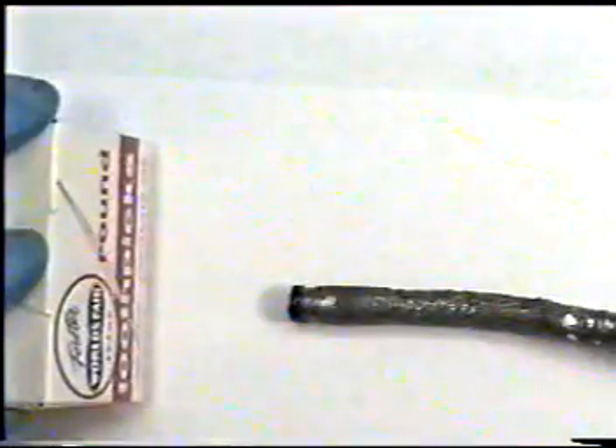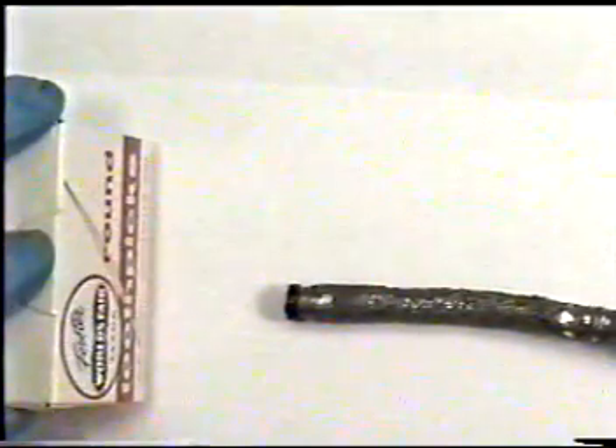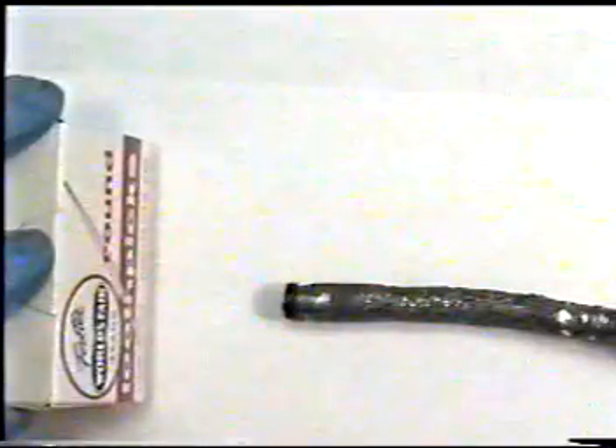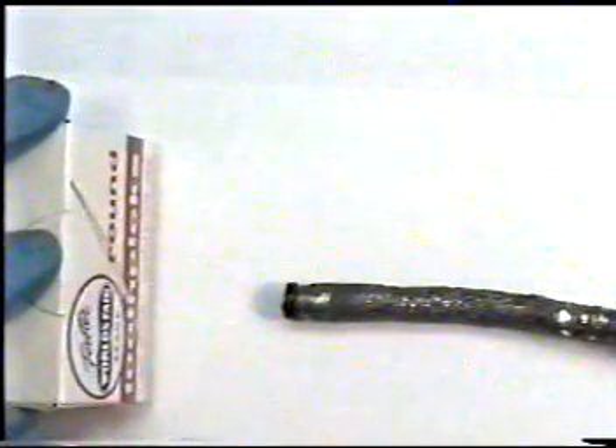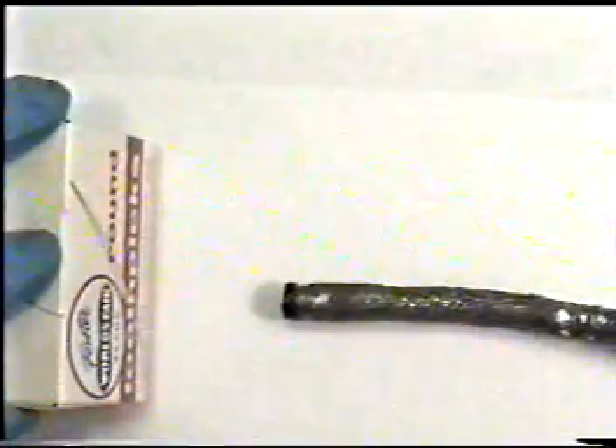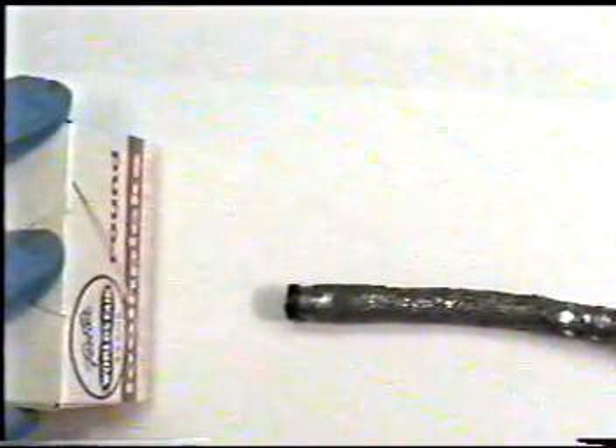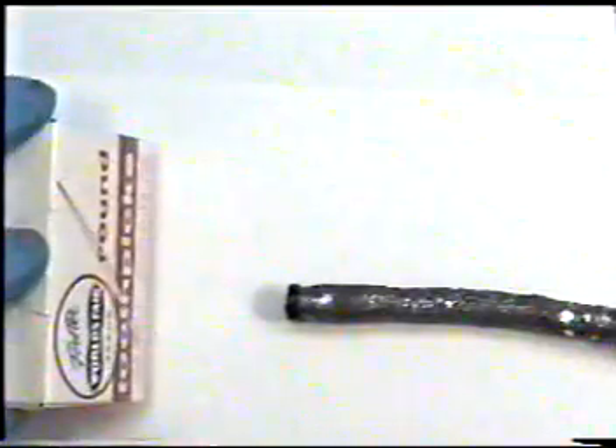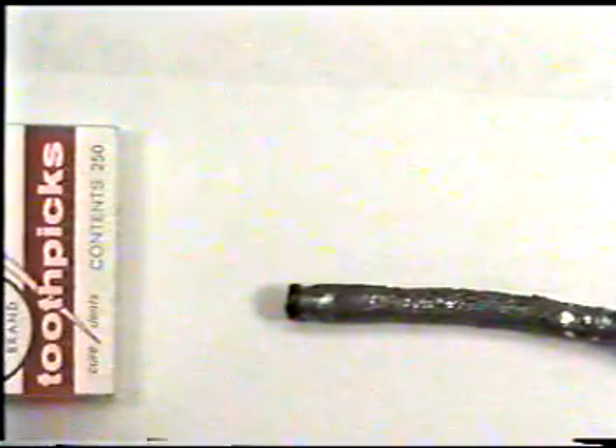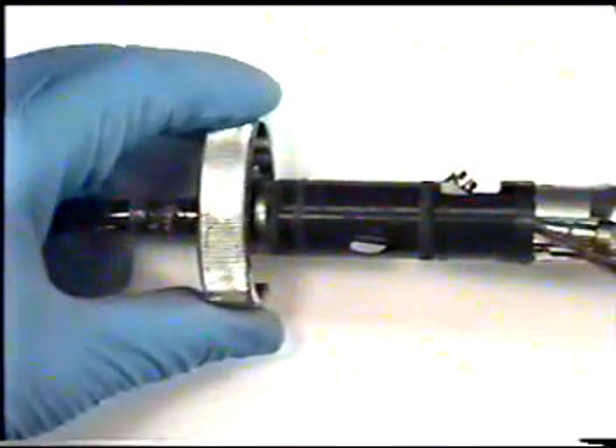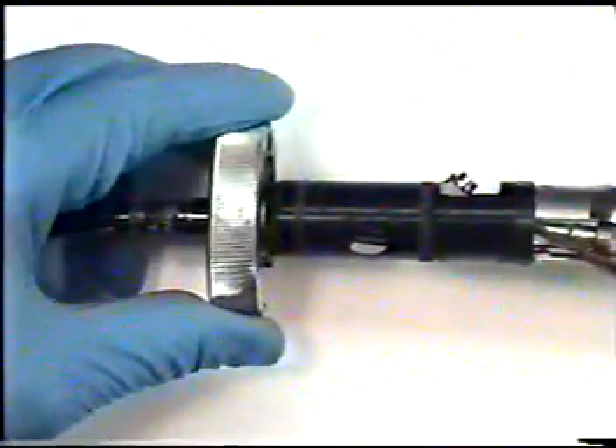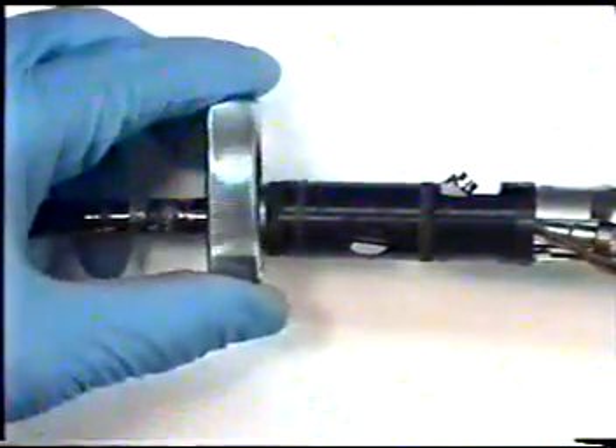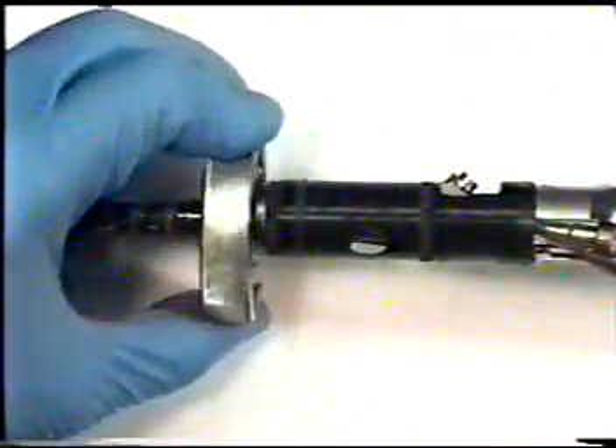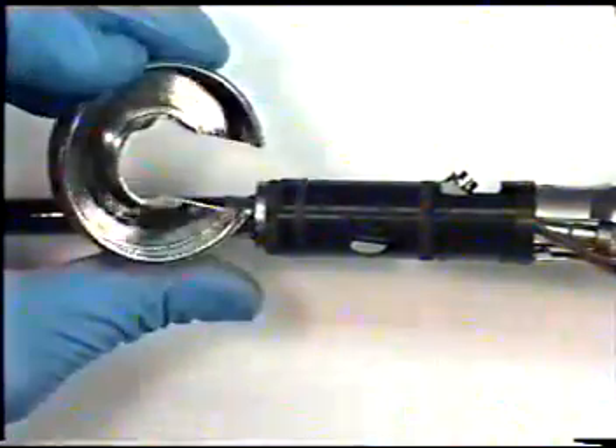the up position by placing an object right side up in front of the distal end and looking on your monitor or through your fibroscope to be sure that when the scope is in up position with the up angulation, you are correctly orientated for the angulation and image. Once you're certain that the correct orientation has been achieved, we can now tighten our insertion tube locking ring to our body control section by hand tightening the locking ring using a special C tool wrench.